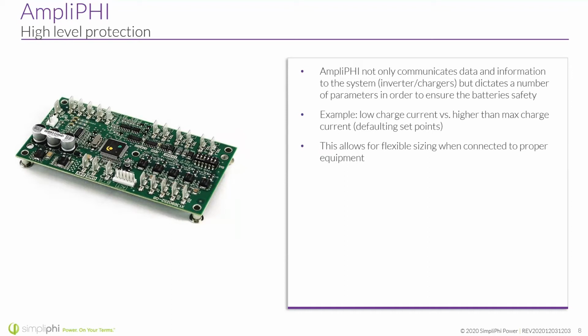An example would be low charge current versus higher than max charge current. This is something interesting our battery management system does. Let's say you tried to set the set point on the inverter paired with our AmpliPhi battery higher than its allowable charge rate based on how many batteries you have. The BMS automatically knows you've gone over the threshold and reverts back to that safe setting. If you try to go lower, it will accept that setting as it sees it as safe. So it's a fail-safe where the BMS in that battery is dictating the system, and that's where it plays a big role in high level protection.